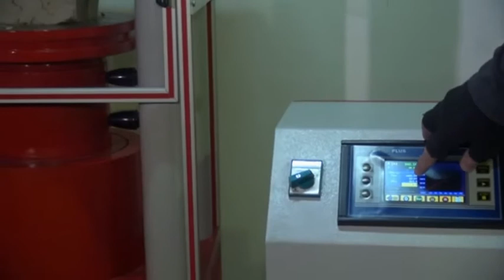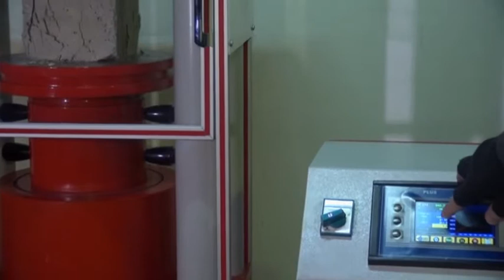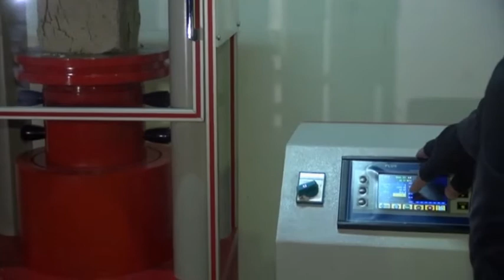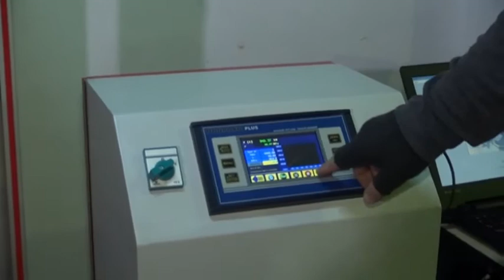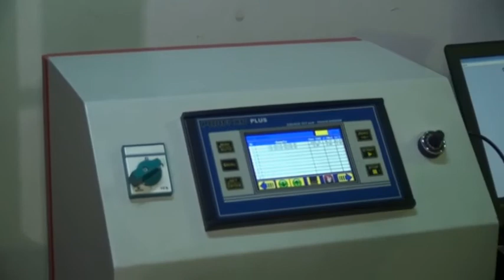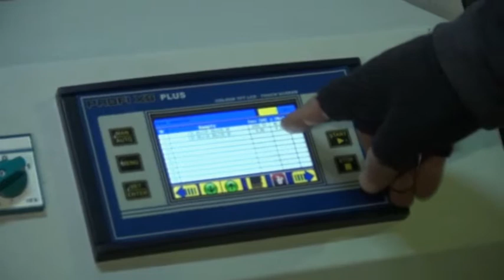So you will see the end of test message, and peak load 1045 kilonewton is stable and fixed on the screen. Also we see the 63 seconds of the test duration. After test finished, we press the test results button, and we see the test results in a table. You see, this is the first test result, is the sample dimension, Fmax the break load, also stress in megapascal, and test duration.